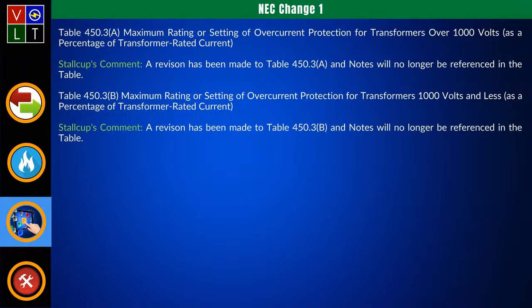Oh yeah, 2023, well that you're talking about HVAC equipment, AC and refrigeration equipment. That's not in 450, it's still in there for transformers. It's still there, but it's mainly referring to the tables and stuff for your percentages for sizing now. The 440.3 you're talking about, there's no sizing percentages there anymore. You got to go to 440.22A to get those sizings for AC and refrigeration equipment. Here in transformers, 450.3 deals with the percentage, using the tables to get your percentages for sizing the transformers.